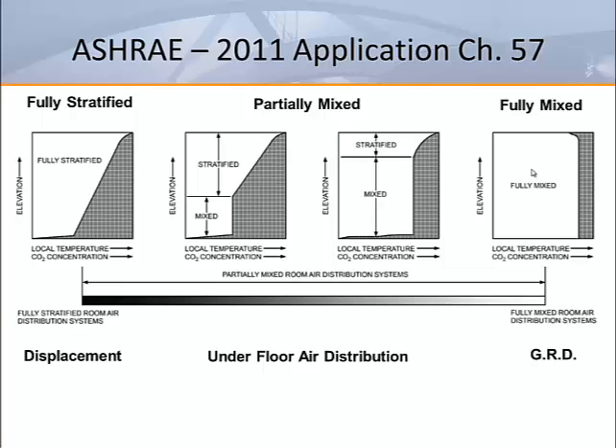This chart from the ASHRAE Fundamentals and Applications Handbook chapters on room air distribution illustrates the temperature stratification profile typical for conditioned spaces. A fully mixed system, such as a ceiling or high sidewall mounted outlet, will mix the entire space so that the temperature measurements during cooling conditions will be consistent from the ankle region up to near the ceiling or the return air intake.